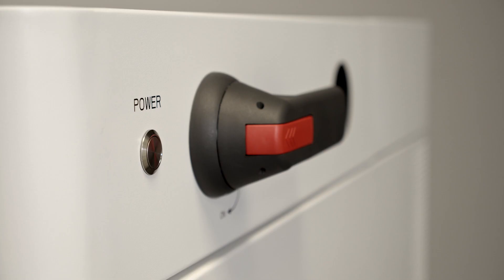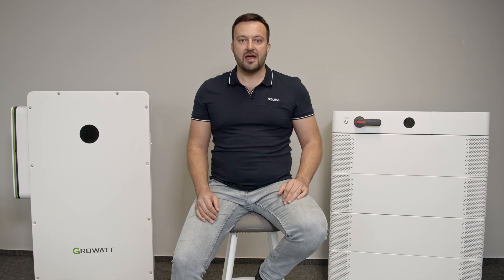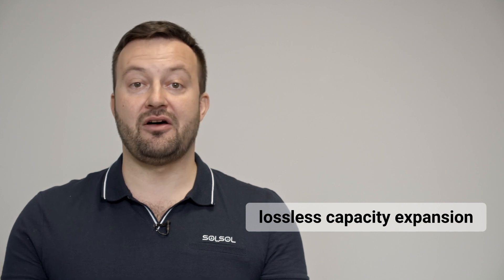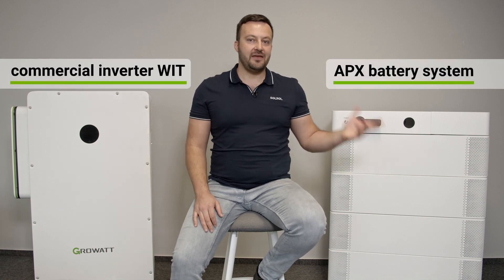The battery has a flexible design with scalable battery blocks with a capacity of 14.3 kWh. The battery capacity is 71 to 200 kWh for one system and supports multiple systems in parallel operation, allowing for great system expansion possibilities without capacity loss. Battery cells are safe and reliable — if one module fails, the others take over its function. The battery is equipped with multi-level protection and automatic balancing, making this a unique combination of Growatt's commercial WIT inverter and APX commercial battery.